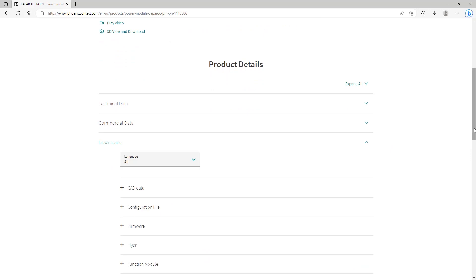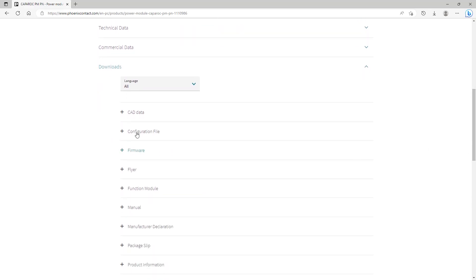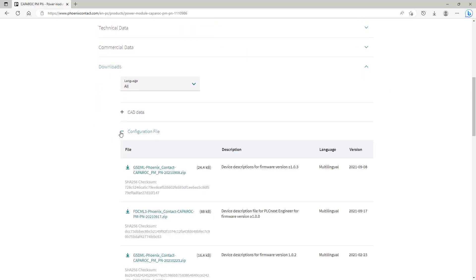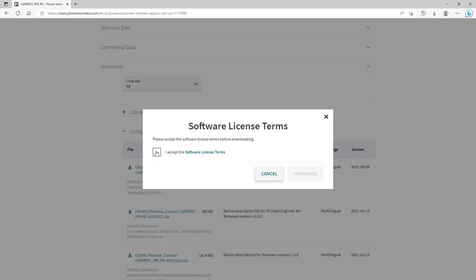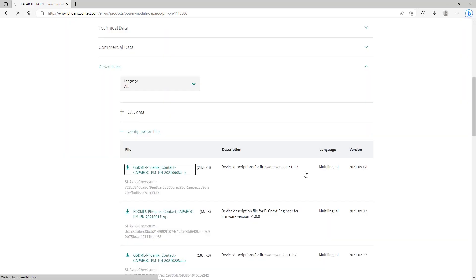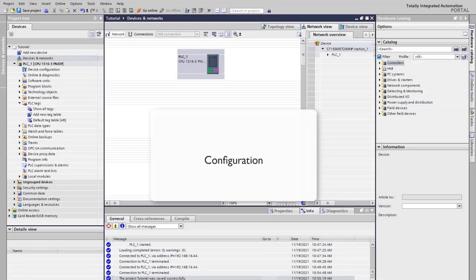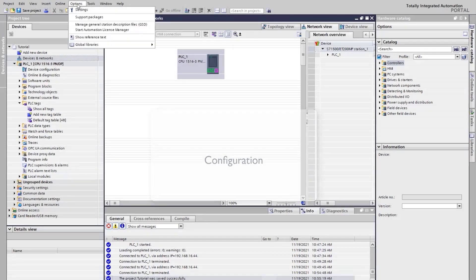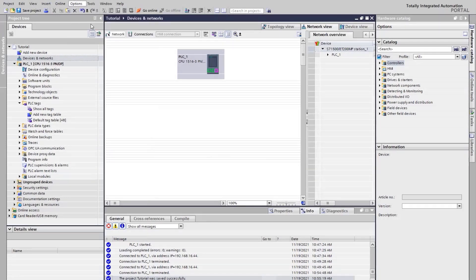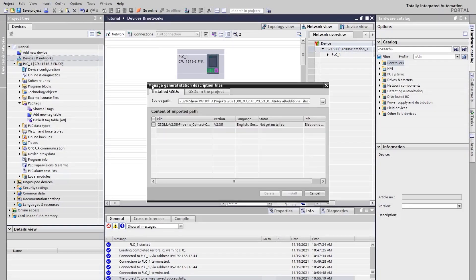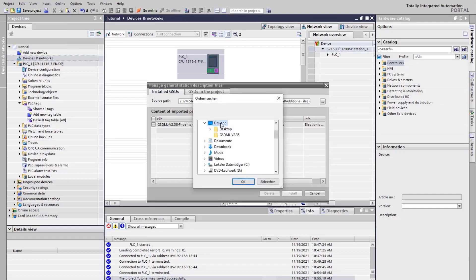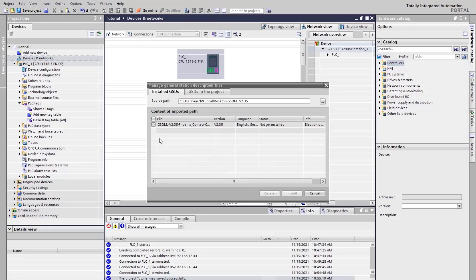Select the file version which fits the firmware of your Caparock system. Before we set up the PROFINET topology in the TIA Portal software, the downloaded GSDML file needs to be integrated into the program. Open the GSD Manager, browse to the previously unpacked GSDML file, select and install it.